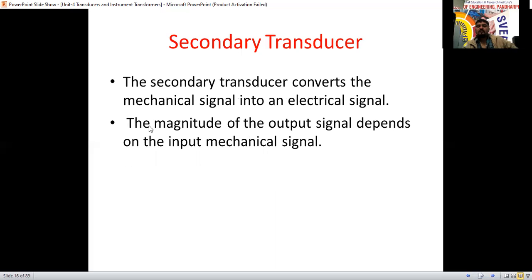The secondary transducer converts the mechanical signal into an electrical signal. In the primary stage, physical quantities are converted into mechanical; in the secondary transducer, the mechanical signal is converted into an electrical signal. The magnitude of the output signal depends on the input mechanical signal. Based on how much input mechanical signal is given, the value of the electrical signal depends on that. Magnitude means the value here.